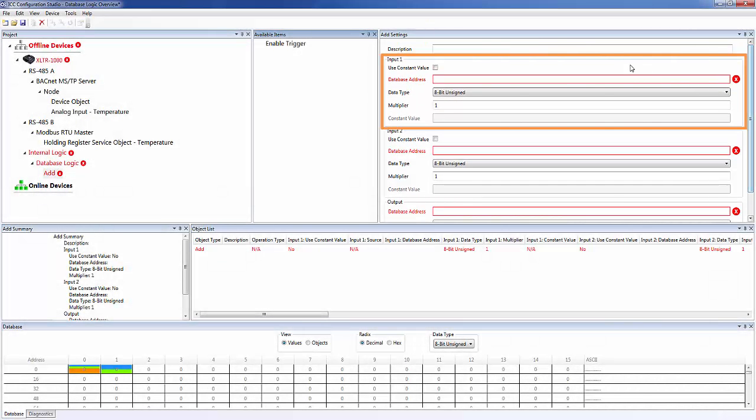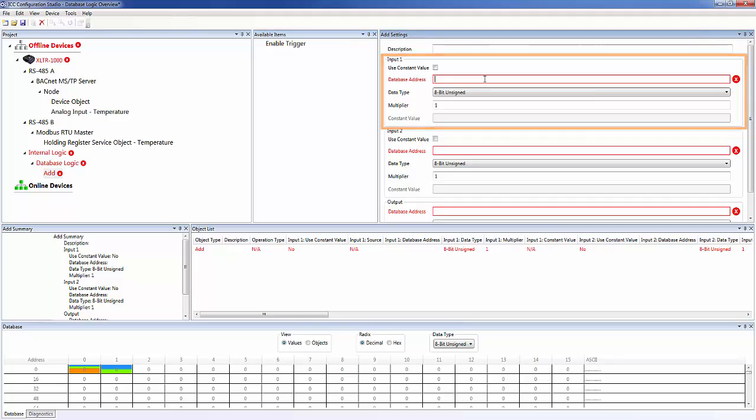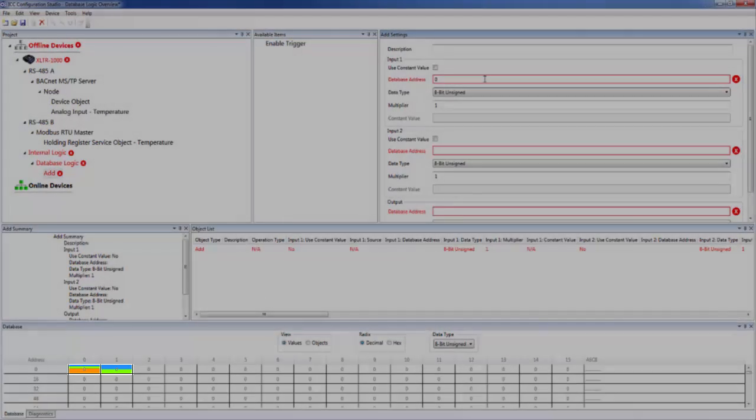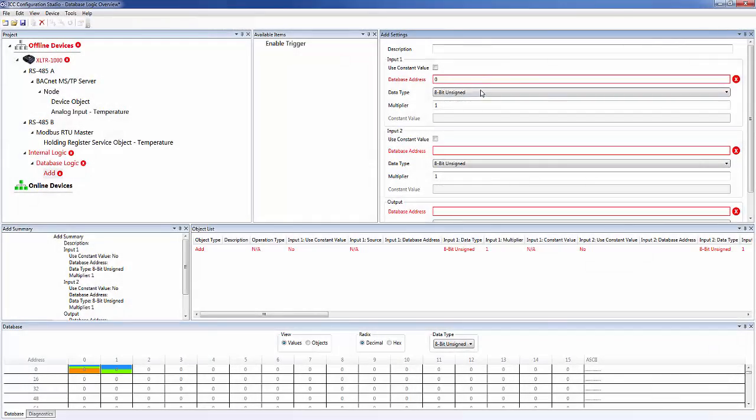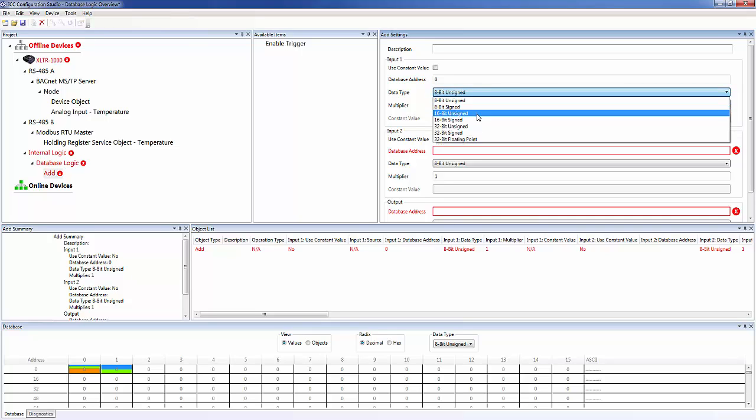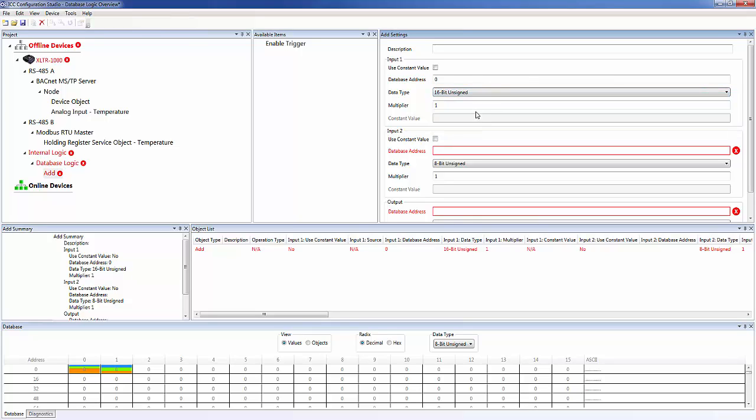For input one, we want to use the temperature read from our Modbus device, which is stored at database address zero. Because this is a Modbus register, the data type is 16-bit unsigned. Now we can enter the multiplier we wish to scale this database value by before performing the add operation.